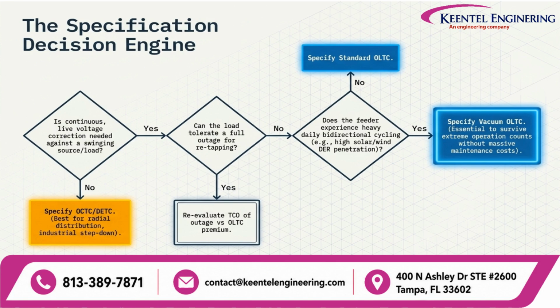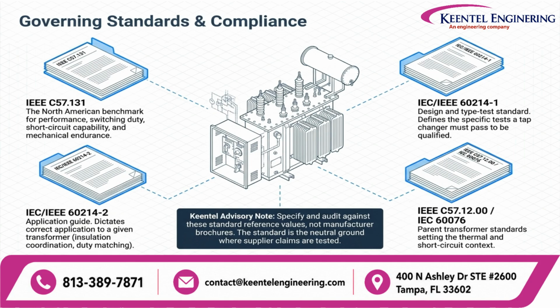Finally, consider budget, maintenance capability, operational flexibility, and future network expansion before making the final specification. This systematic approach minimizes lifecycle costs while maximizing operational performance. The IEC 60214 series defines design requirements, testing procedures, operational performance, and maintenance expectations for tap changers. IEEE standards provide additional guidance for transformer applications, diagnostics, maintenance practices, and field testing.